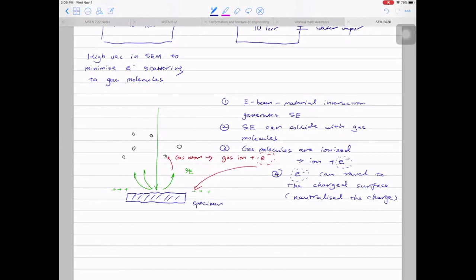In environmental SEM, samples are placed very close to the objective, giving a very small working distance. The reason is you don't want the primary electrons to interact too much with the gas molecules. Also, you cannot use a regular SE detector — environmental SEMs need a dedicated environmental secondary electron detector. With environmental SEM you can do a lot of fancy in-situ work to look at hydration and dehydration inside the SEM.